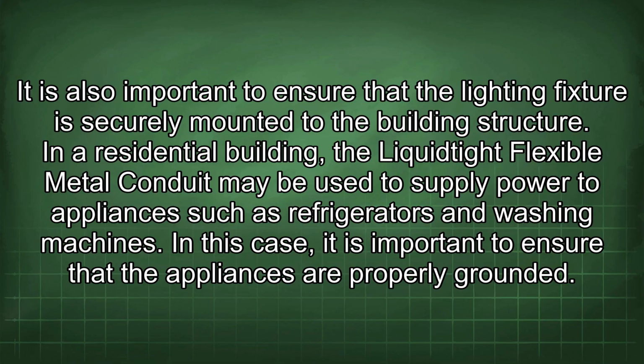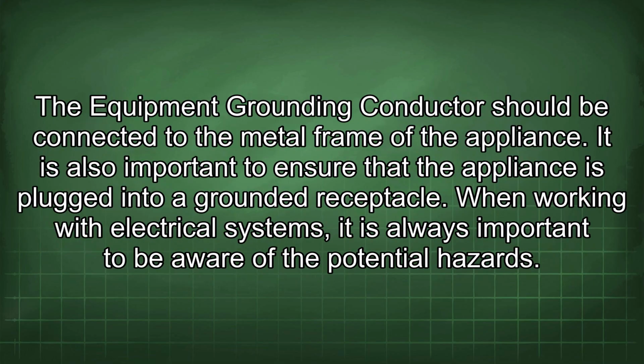In a residential building, the Liquidtight Flexible Metal Conduit may be used to supply power to appliances such as refrigerators and washing machines. In this case, it is important to ensure that the appliances are properly grounded. The equipment grounding conductor should be connected to the metal frame of the appliance. It is also important to ensure that the appliance is plugged into a grounded receptacle.